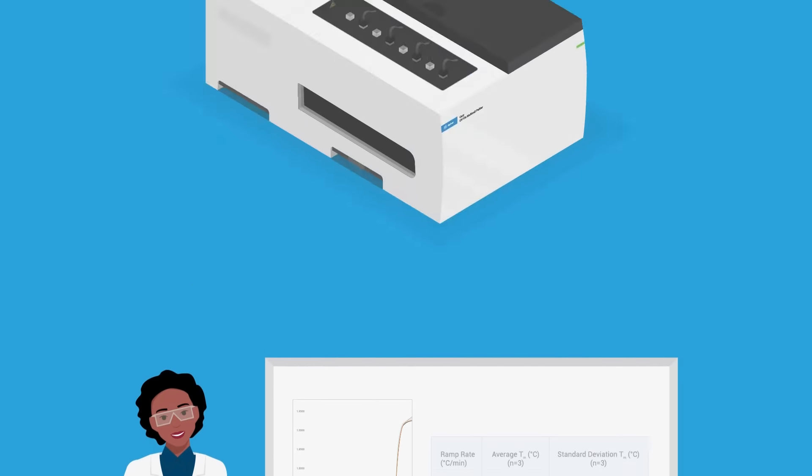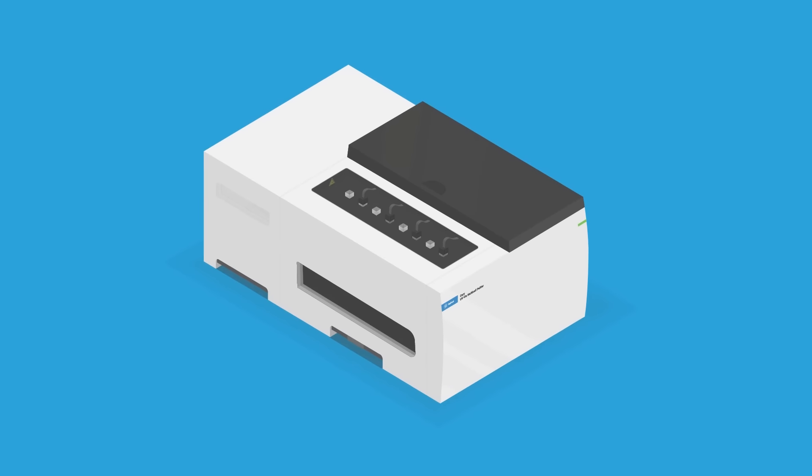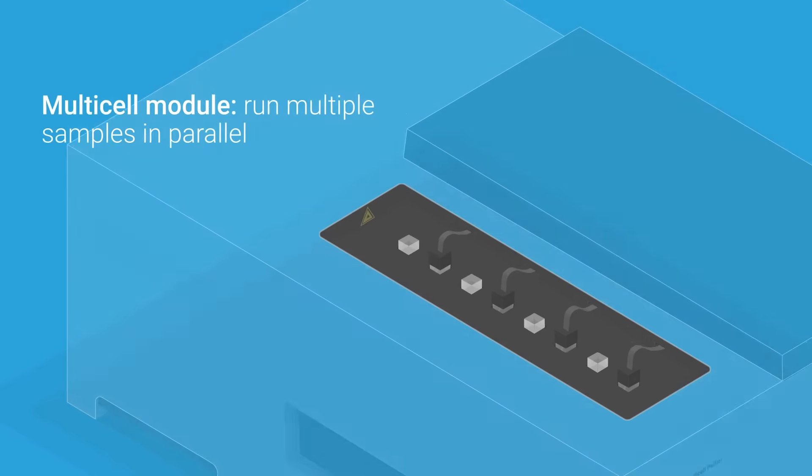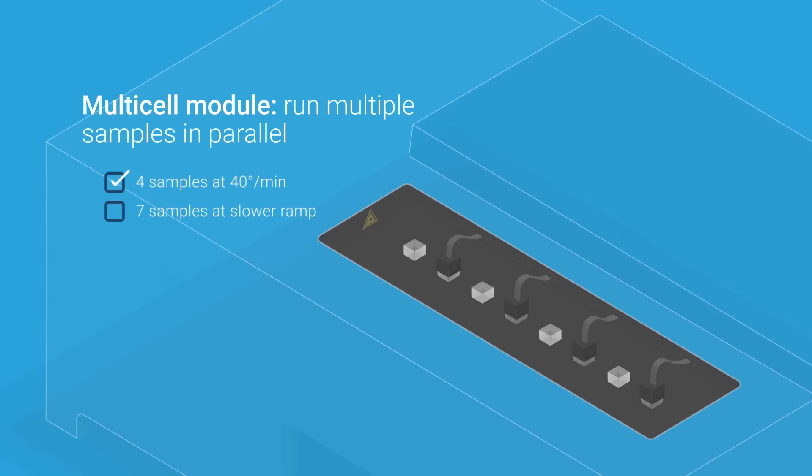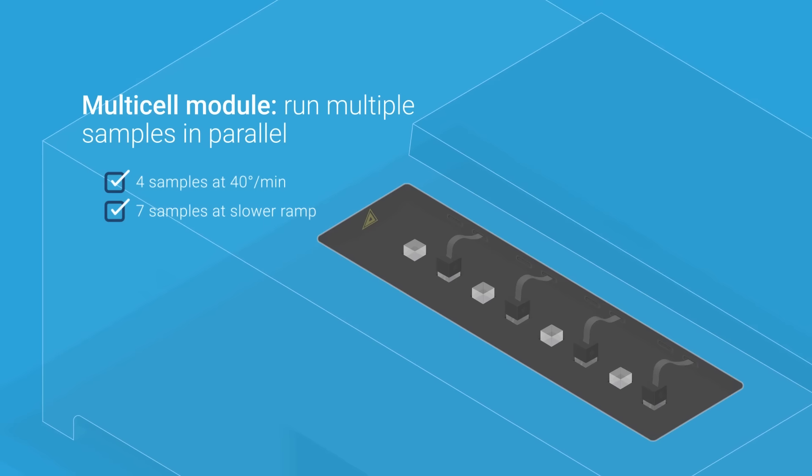The Cary 3500 also features a multi-cell holder that allows Alice to run 4 samples in parallel, up to 40 degrees per minute, or 7 samples for slower temperature ramps.